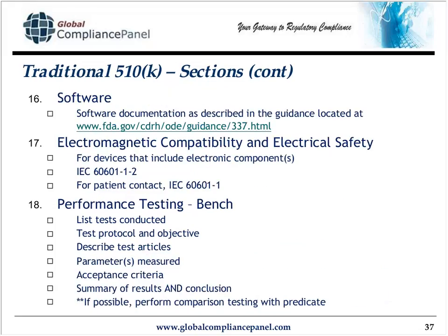Section 16 is software. If your device is software driven, you've got to make sure that you include documentation as provided in the software guidance document. Any EMC or electrical safety information is Section 17. Any bench performance testing, that's your in-house non-clinical testing. So you've got to make sure that your validation and verification testing is included in here.